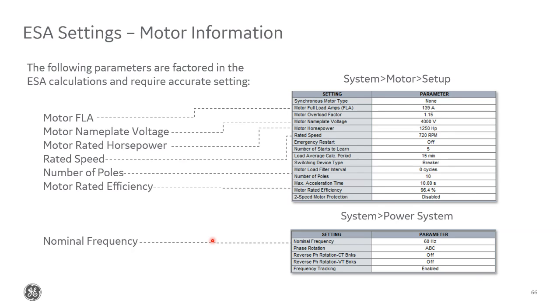When it comes to the settings, there's just a few windows that you need to look at. The first is, obviously, we need to have all of your motor information properly set. So under the system menu, motor setup, you'll see a window like this. And specifically for ESA, what we're interested in getting accurately set is the motor FLA, the motor nameplate voltage, the horsepower, speed, number of poles, and the rated efficiency. With the newer firmware, these last two aren't as critical. We definitely need this top group though. And then quite simply, I'm sure you'll have this set up anyway, but under system, power system, we also use this nominal frequency set point.